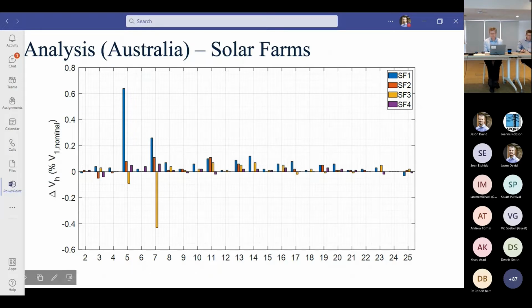Given the substantial change, particularly at the 7th harmonic, we see about a change of 0.4% of the nominal voltage. That would suggest there's some degree of harmonic sinking at the site, whether through filtering or potentially just the passive components—say the transformers, the collector network—acting as a harmonic current sink for that particular area. That's about all I can say.